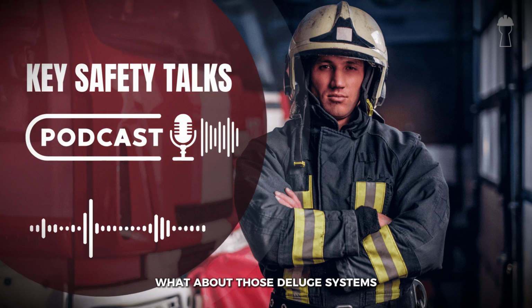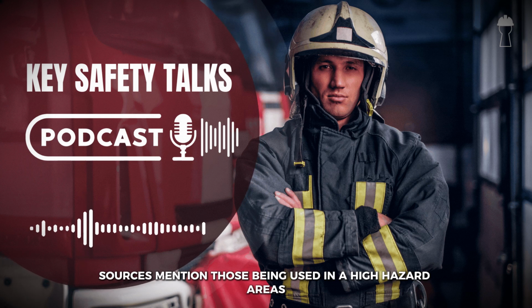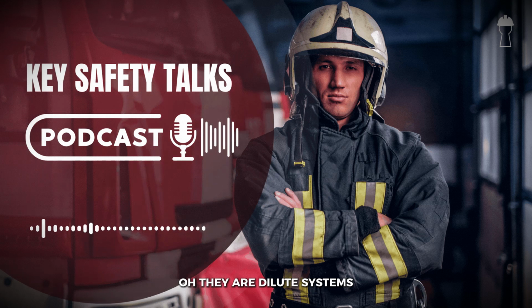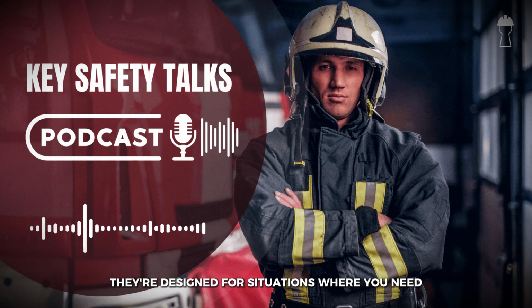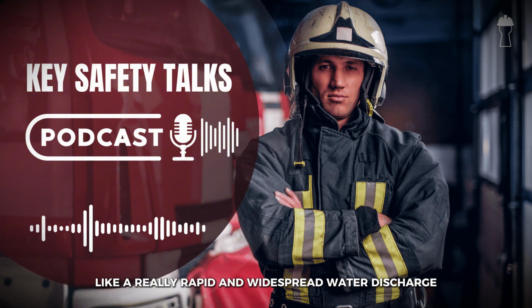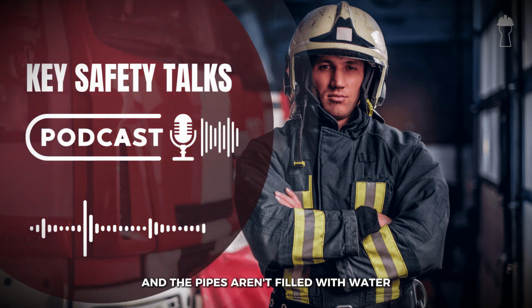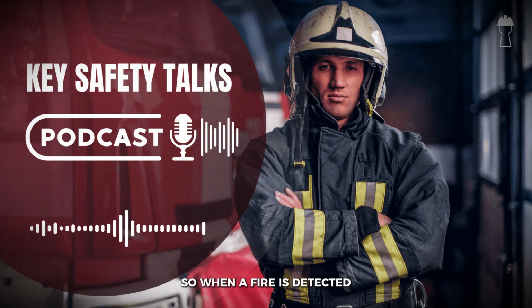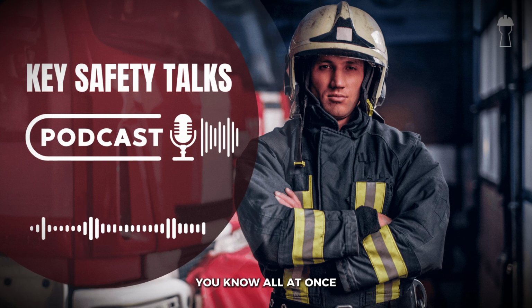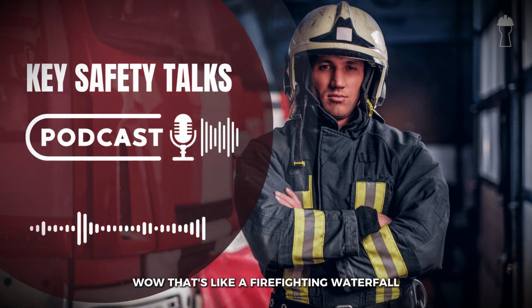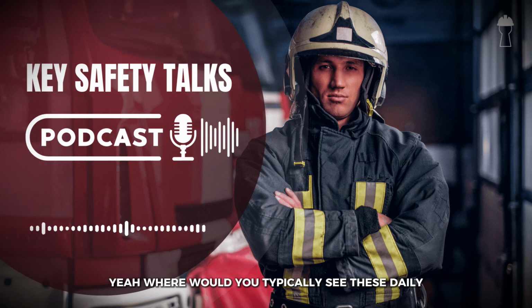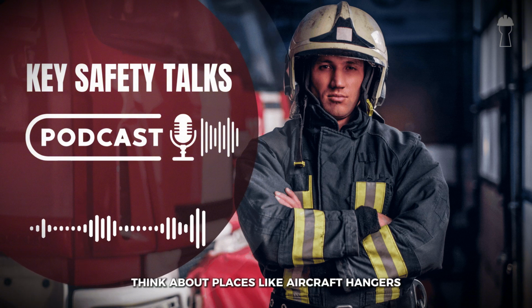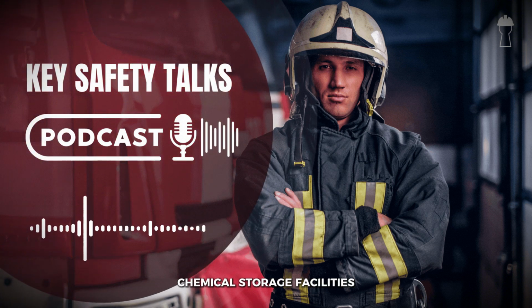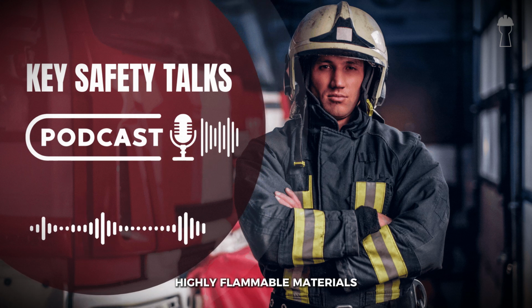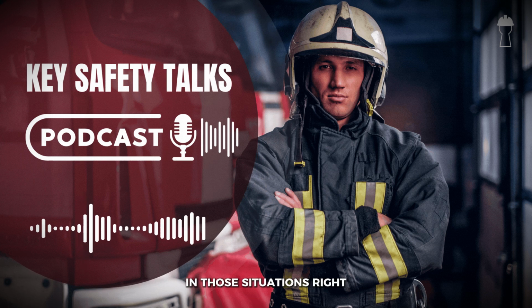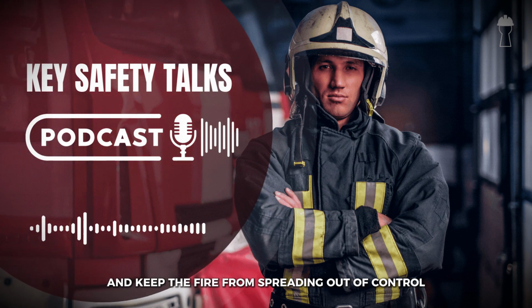What about those deluge systems? Our sources mention those being used in high-hazard areas. They sound pretty intense. Oh, they are. Deluge systems are designed for situations where you need a really rapid and widespread water discharge. So all the sprinkler heads are actually open and the pipes aren't filled with water until the system is activated. So when a fire is detected, a massive amount of water is released all at once, completely drenching the entire area. Wow, that's like a firefighting waterfall. Where would you typically see these deluge systems being used? Well, think about places like aircraft hangars, chemical storage facilities, or areas with highly flammable materials. You want to suppress that fire as quickly and completely as possible in those situations. Right, minimize the damage and keep the fire from spreading out of control.